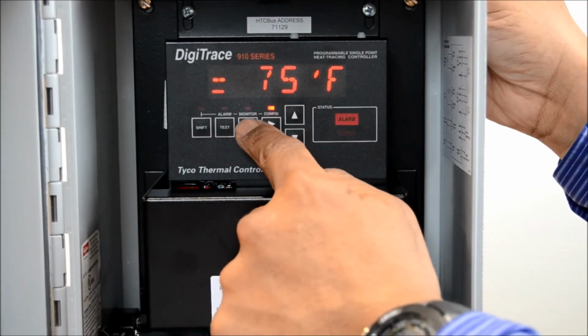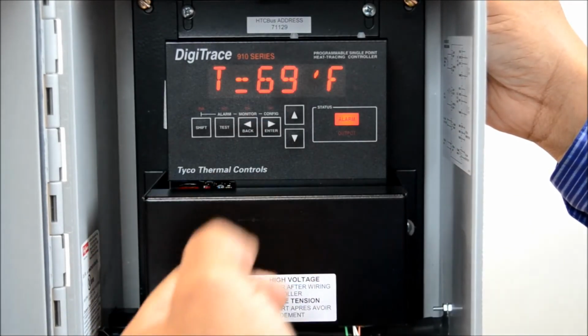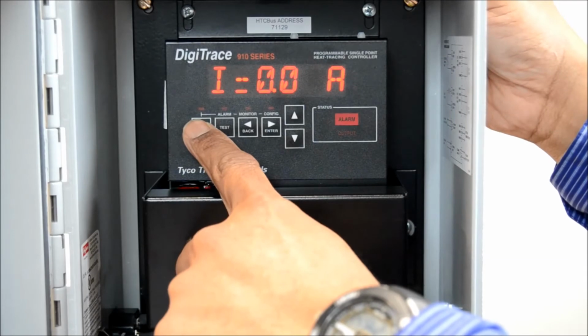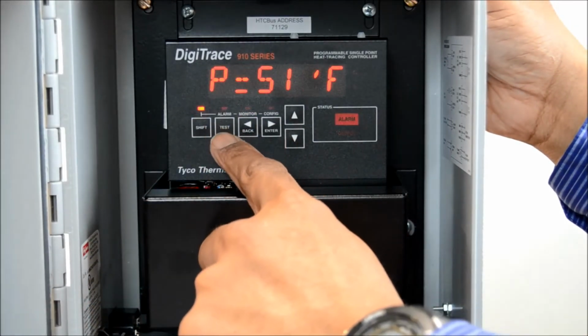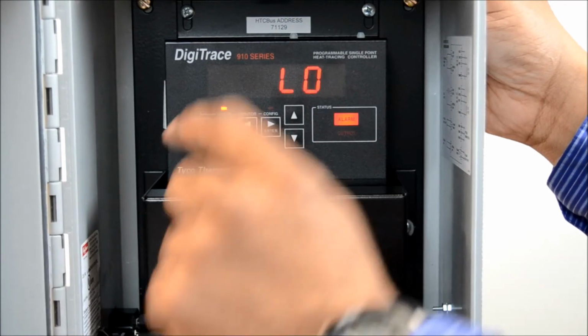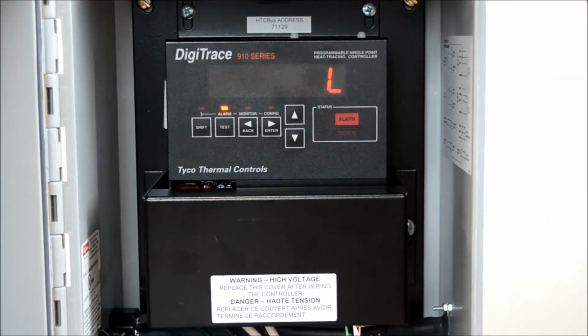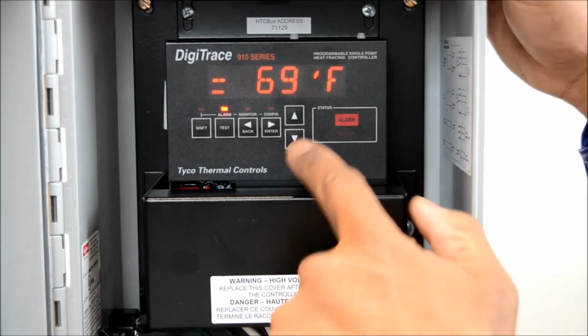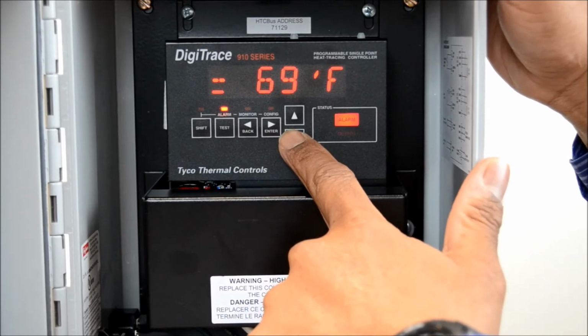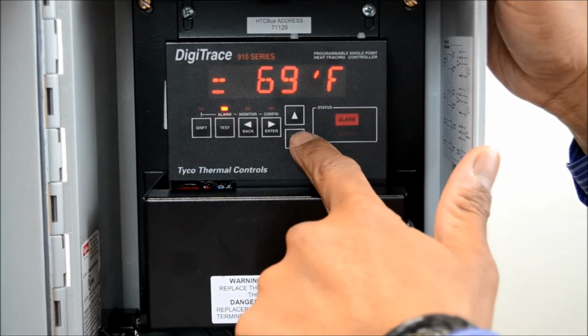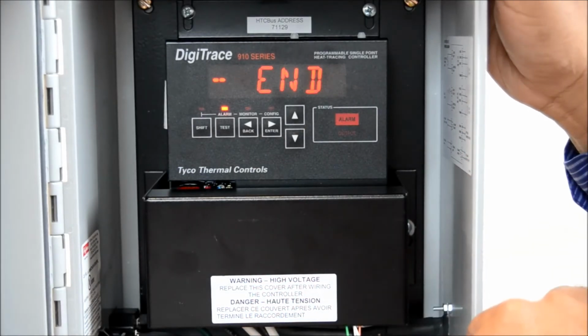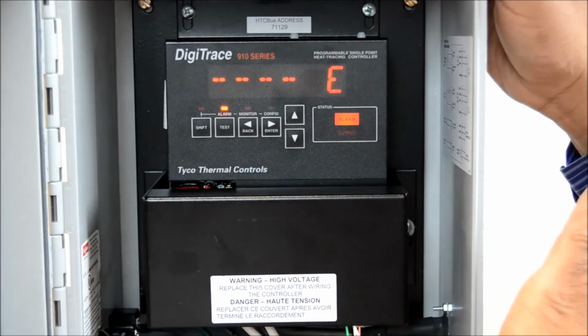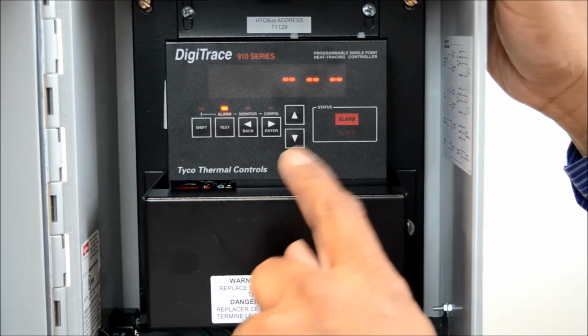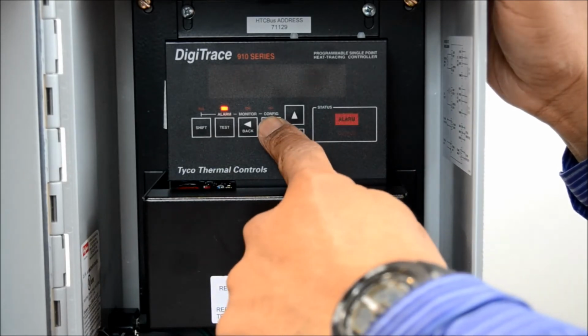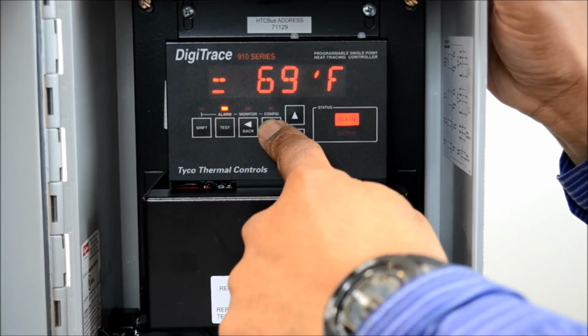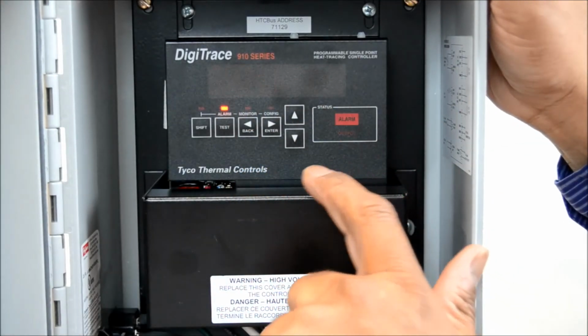Now, in order to try to clear this alarm, let me hit back first to get out of the program. When you see an alarm, you'll have to hit Shift and then the next button over, which is the alarm button, or it says test on there. And this display now reads exactly what the alarm is. Now you can go up and down this menu to see all of the alarms that may be on the system right now. So right now we have a low temperature alarm, and then if I hit down, you see N there, so that means there are no more alarms. Now generally, in order to try to clear an alarm, I would go to enter and hit enter. It says low temperature alarm 1. You hit enter again and it asks you if you want to reset this, and then yes.